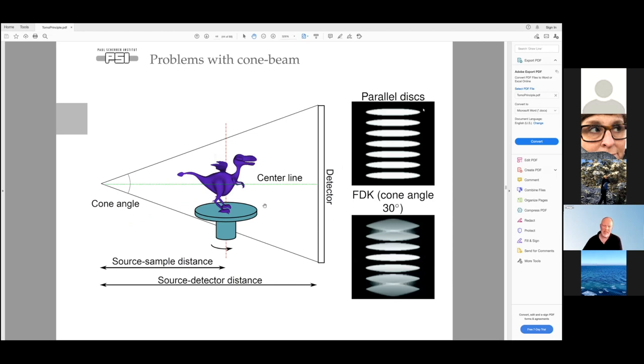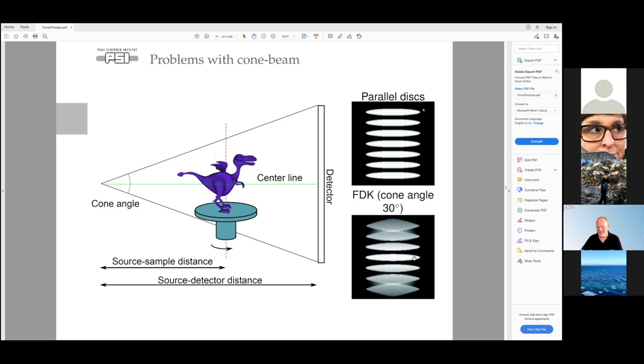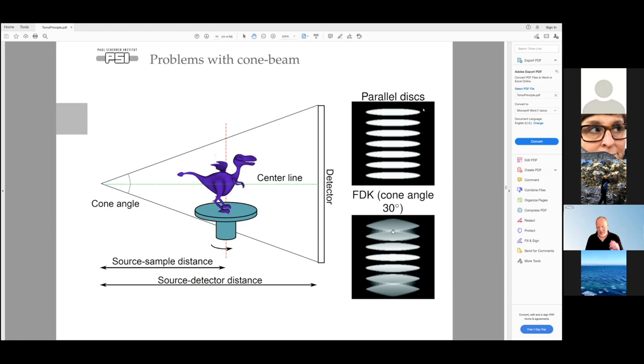Cone beam reconstruction is non-trivial. One commonly used approximation is defined by Feldkamp — it does a pretty good job, but you should try to have a very shallow cone angle. The wider the cone angle, the more artifacts you can expect. With cone beam, only the central slice is exact; the rest has some distortion. A stack of discs — the so-called 'Feldkamp killer' — shows this: with a 30-degree cone angle, you get a nice reconstruction in the middle, but as you move away from the central slice you get really ugly cone beam artifacts. You should try to get magnification by putting the source and detector further apart, giving a narrower cone angle and better images.